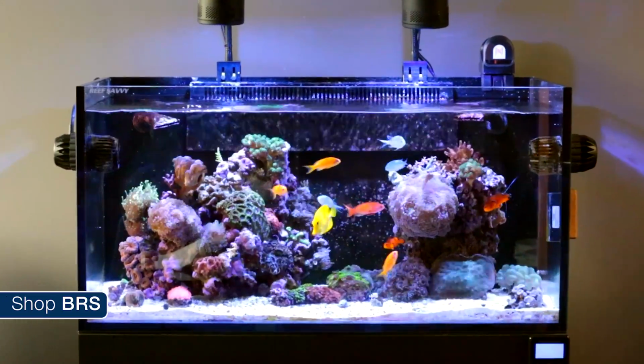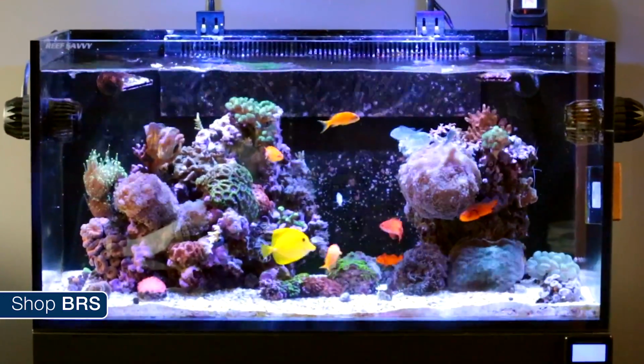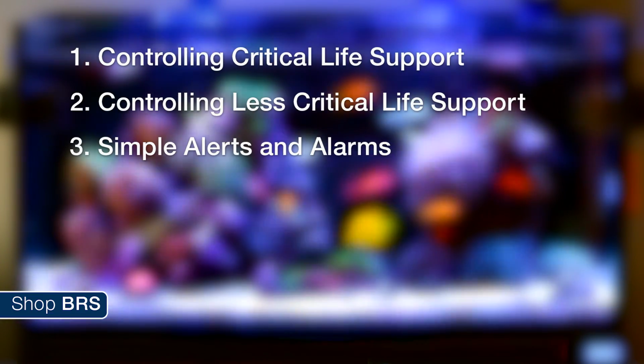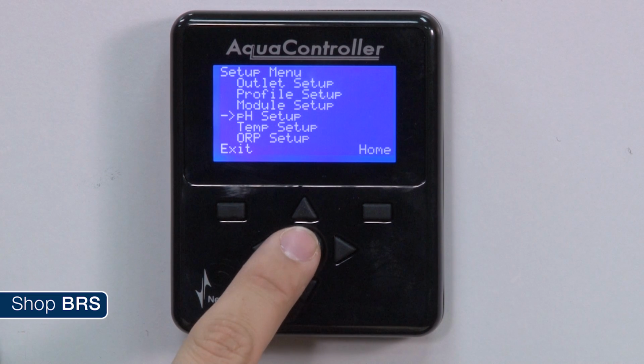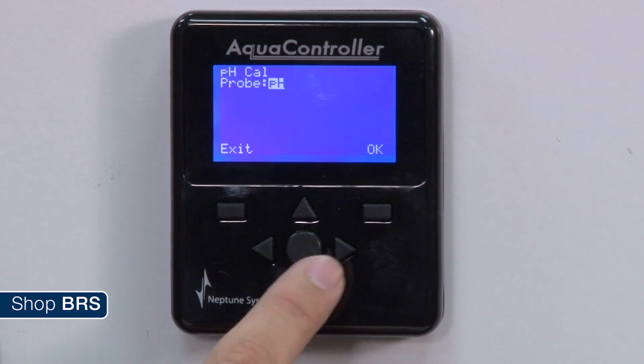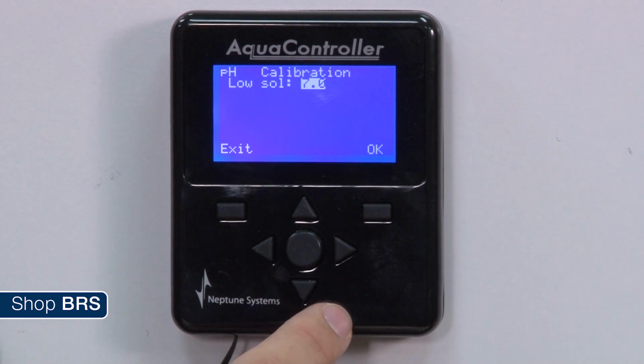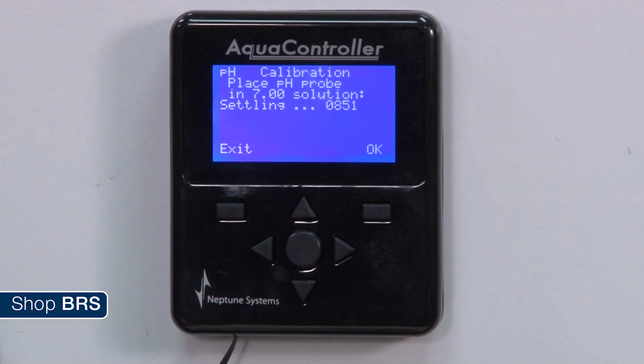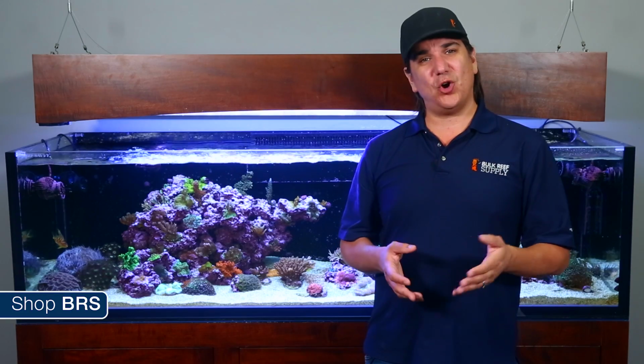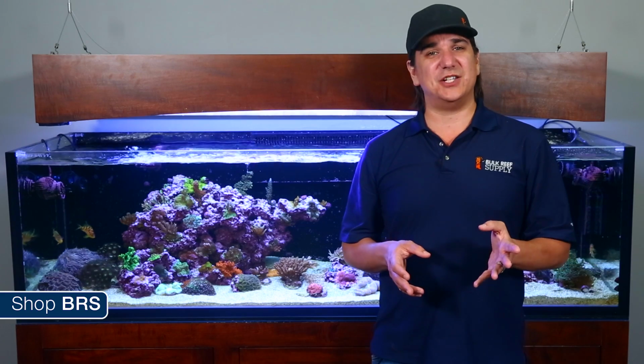That's not the case for most of us, so I'm going to refine the answer based on three common types of use: controlling critical life support, controlling less critical life support, and simple alerts and alarms. Calibrating your probe takes about 5 minutes and costs around $2, so in general I'd suggest calibrating them every 3 months as a blanket statement. If you're using a decent probe, that should be more than adequate. However, you can apply some basic logic behind that to do them more or less frequently as well.